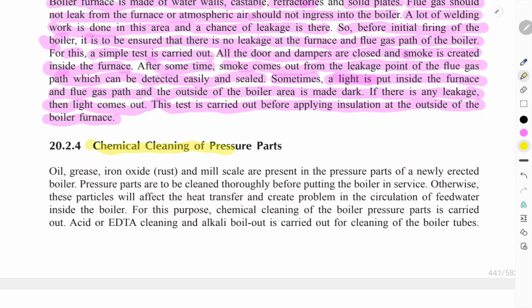Chemical cleaning of the pressure parts. Okay, so we will see chemical cleaning. Oil, grease, iron oxide rust and mill scale are present in the pressure parts of a newly erected boiler. The boiler pressure parts are to be cleaned thoroughly before putting the boiler in service. Otherwise, these particles will affect the heat transfer and create problems in the circulation of feed water inside the boiler. For this purpose, chemical cleaning of the boiler pressure parts is carried out.